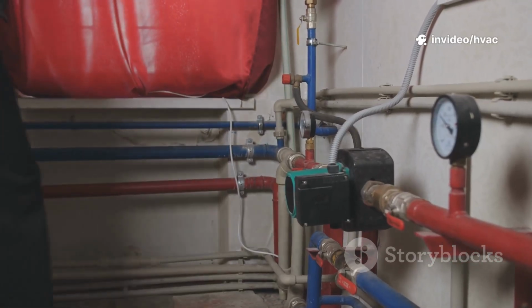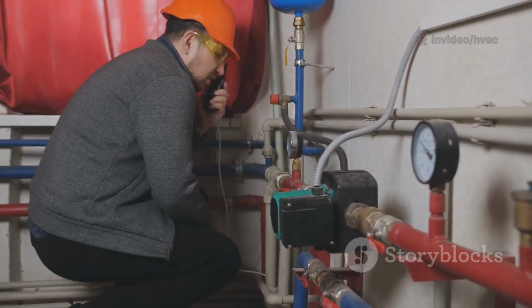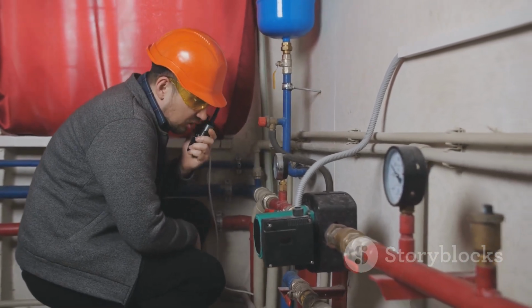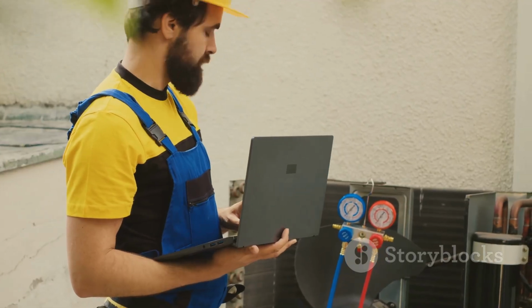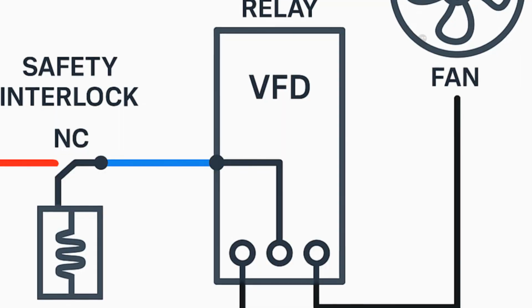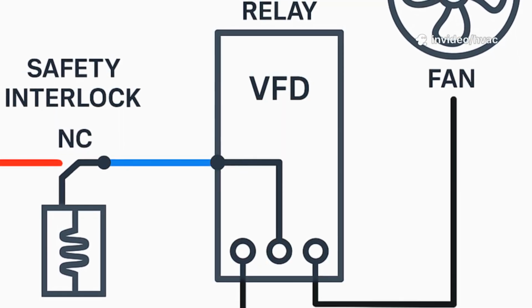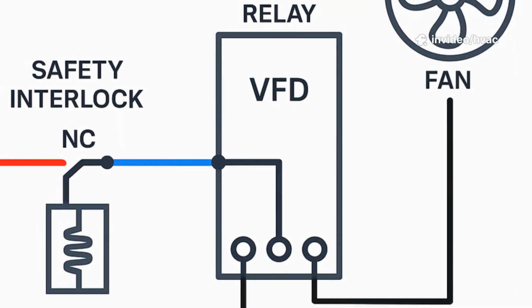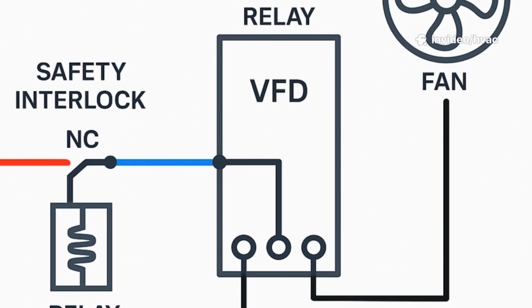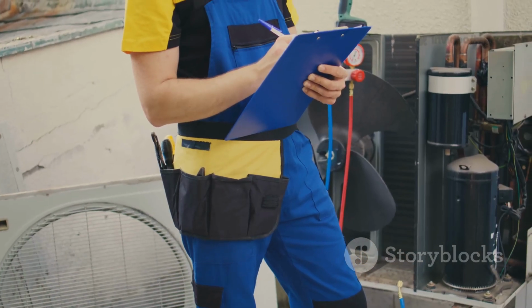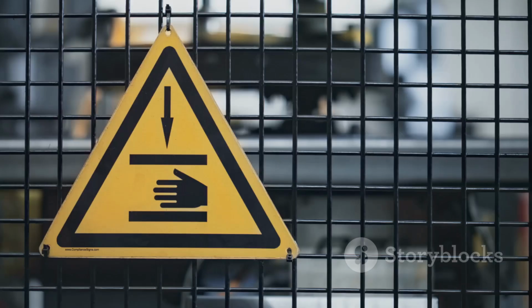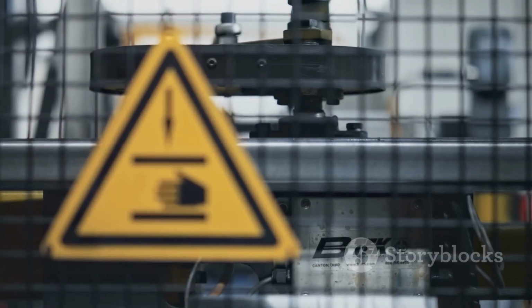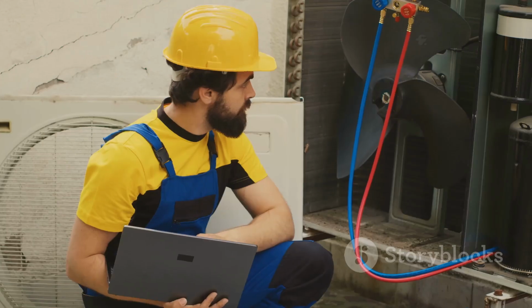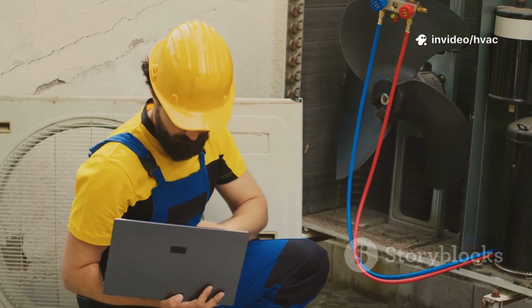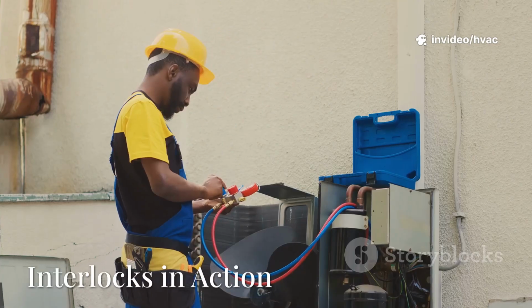Interlocks prevent cascading failures. If a pump fails, the boiler shuts down, avoiding explosions. They isolate faults, containing problems before they escalate. Interlocks also improve efficiency, like ensuring heaters only run when fans are on, preventing overheating and nuisance shutdowns. This reduces maintenance and increases reliability. Interlocks are life-saving, cost-saving, and should never be bypassed. They're the cheapest insurance you can buy for your system. That's real protection.